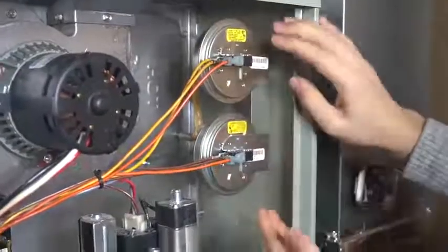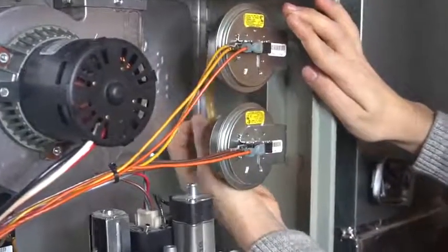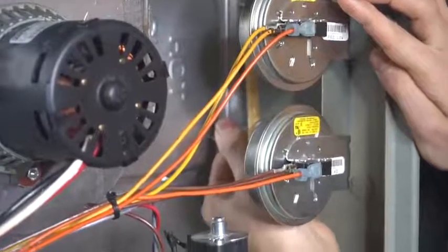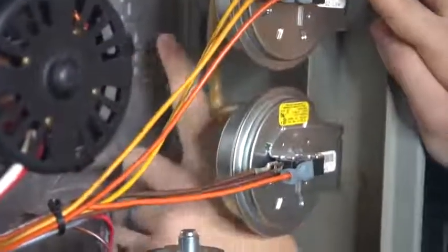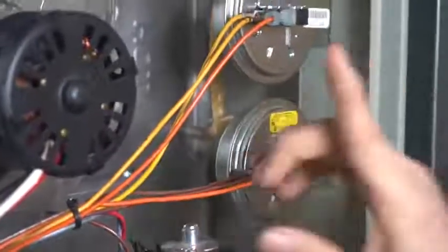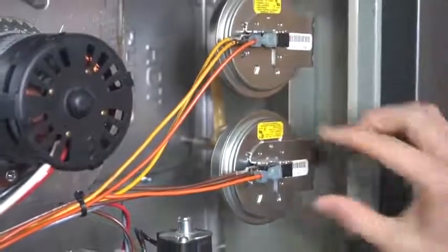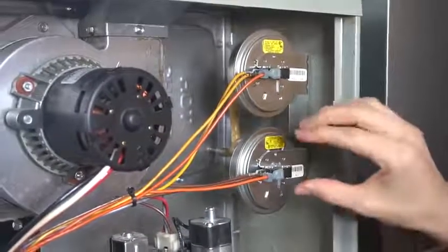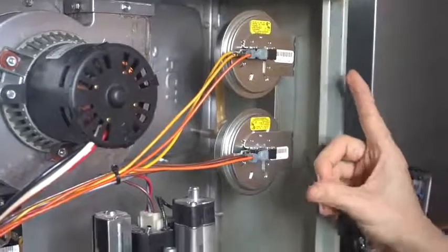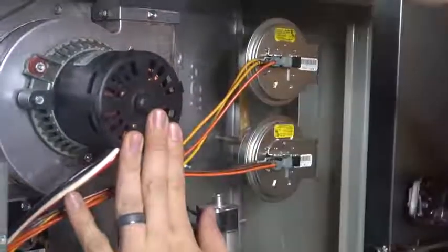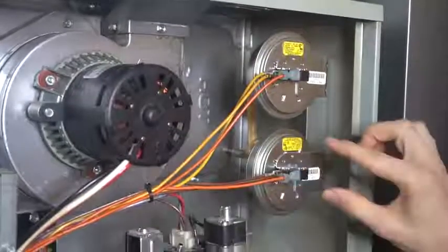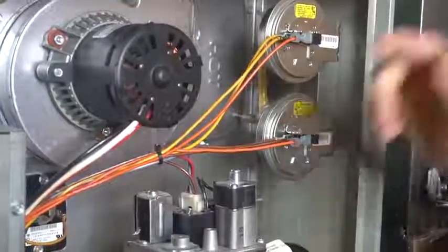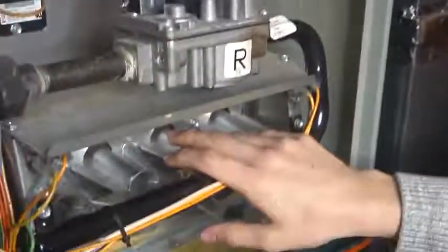And the way it does that is through these pressure switch tubes, or hoses. And these tubes are usually attached to either the inducer motor housing or a collector box, if you have one. And as the air is going through the heat exchanger and out the exhaust pipe, there's a pressure difference, and this pressure switch gets closed on a pressure differential, which means this switch here is normally open, but whenever the inducer motor turns on and starts exhausting air, that pressure difference that it creates actually closes this pressure switch. And then the electric circuit gets sent through it, and then the gas valve is powered up and the burners light, and everything goes from there.